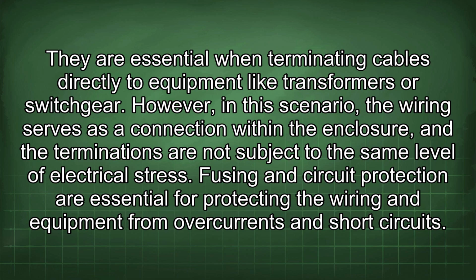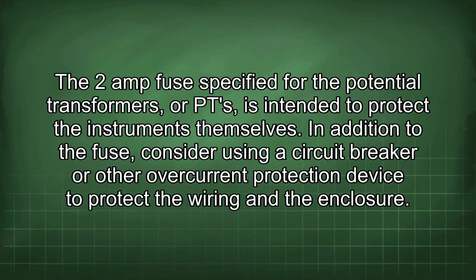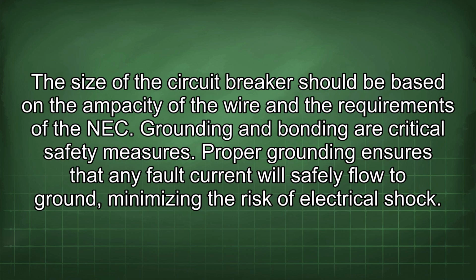Fusing and circuit protection are essential for protecting the wiring and equipment from overcurrents and short circuits. The 2 amp fuse specified for the potential transformers, or PTs, is intended to protect the instruments themselves. In addition to the fuse, consider using a circuit breaker or other overcurrent protection device to protect the wiring and the enclosure. The size of the circuit breaker should be based on the ampacity of the wire and the requirements of the NEC.